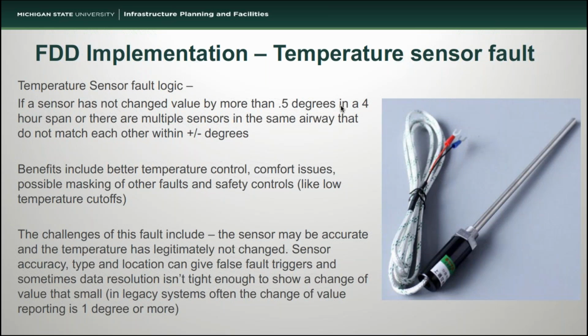Now, the challenges of a fault like this, sometimes the temperature has just legitimately not changed. There is nothing wrong with the operation of the unit. It's just how it's operating right now. And you may get a fault even though everything's just fine. Sensor accuracy, type, and location also play an important role in this. If you have an inappropriate ranged sensor or it's in a bad location, it could indicate that there's a problem that maybe doesn't actually exist for the operation of the unit. And then finally, one of the challenges we have is with our legacy systems, sometimes they don't report a change of half a degree. It may be a degree or 2 degrees. And then again, you'll have a fault trigger for that particular sensor that's not necessarily really a problem. Just because it hasn't changed doesn't mean that it's reporting inaccurately. Next slide.